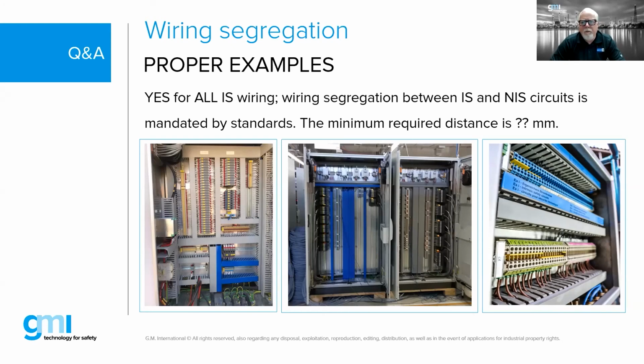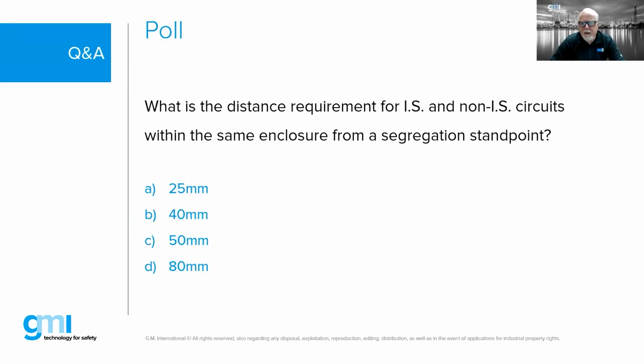Or if one or both of the cables are armored or shielded, then we can put IS and non-IS cables right next to each other, right? So there are some exceptions to that 50 mil separation between IS and non-IS. But on the inside of panels, we want to keep a minimum of 50 mil separation. And this is to keep the inductive currents from traveling from the non-IS into the IS side and interfering with it. Yeah, and that was the question, but we gave it away.